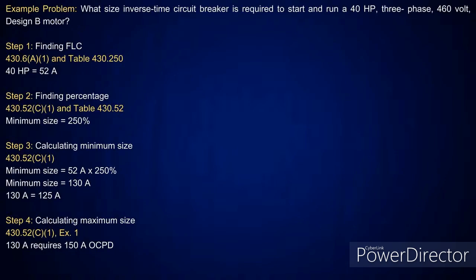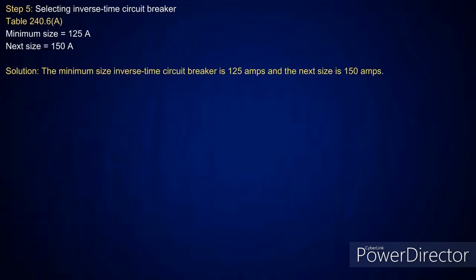It tells you to take it at 250%. So you take the 52 amps at 250%, which gives you 130 amps. It says you can't exceed the calculated load, so I have to drop down to 125 amps. Then Exception 1 allows me to go up to the next standard size if the motor fails to start due to inrush current, and per Table 240.6(A), that'd be a 150 amp overcurrent protection device.